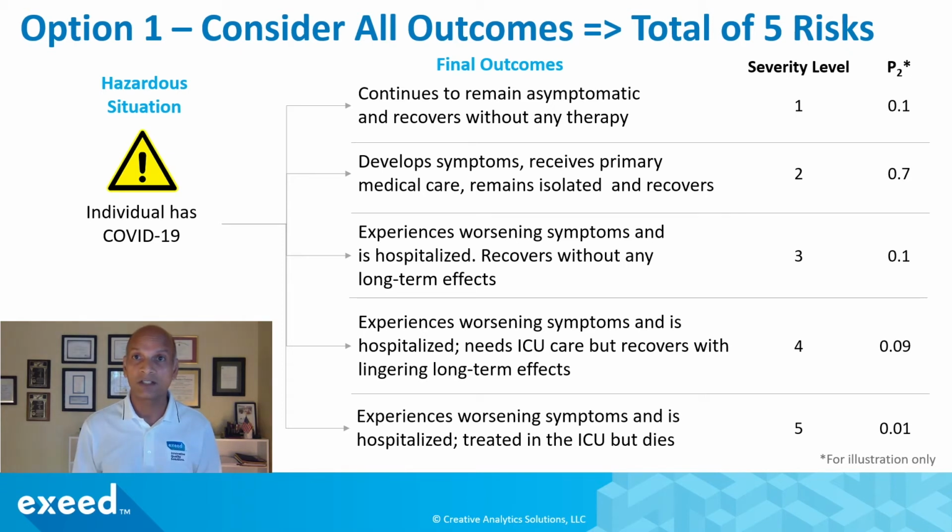So here you have a distribution. You could consider all 5 scenarios as 5 different risks for the same hazardous situation. And this method is described in this great book I would recommend to all of you. It's Safety Risk Management for Medical Devices by Bijan Elahi.